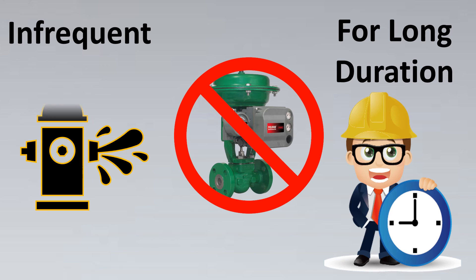If your valve or your sigma or cavitation index value falls in this range, you can use it for infrequent operations - like when you go for a relief valve case, or you can use it for control valve during startup operations or during shutdown operations, but it cannot be used for long duration of applications.